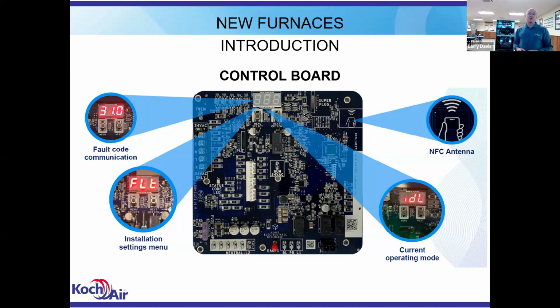Unfortunately, to do that on the mid tier, you have to change the board out. On the communicating systems, you can do an over-the-air software update to the board through the communicating wall control. But on the mid tier, there's currently not a way to field update the software in the board. So that's the only way to deal with those codes. And if you have not experienced that in the field, it'll make a little more sense when we get into the slides about the IntelliSense.